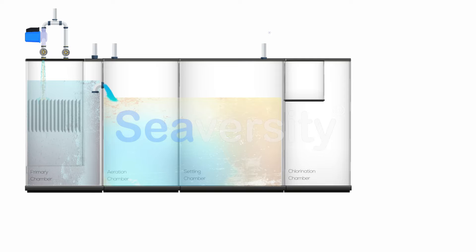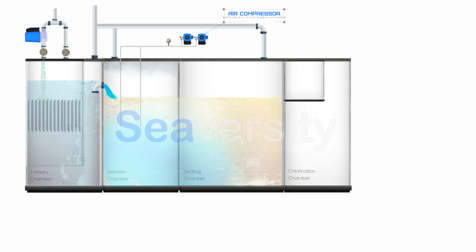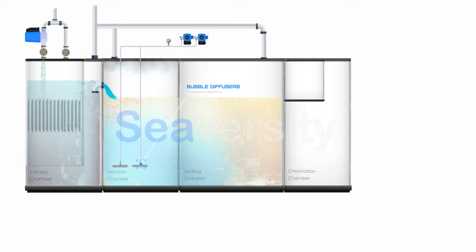The carbon dioxide is emitted throughout the vent system, whilst the water, together with the bacteria cells, are displaced into the settling compartment. Air is supplied to the sewage from a rotary compressor through a number of fine bubble diffusers located at the bottom of the tank, but removable from the side for ease of maintenance. The air provides the life-giving oxygen to the aerobic organisms, and also keeps the contents of the tank intimately mixed with the incoming raw sewage and the returned settled activated sludge.